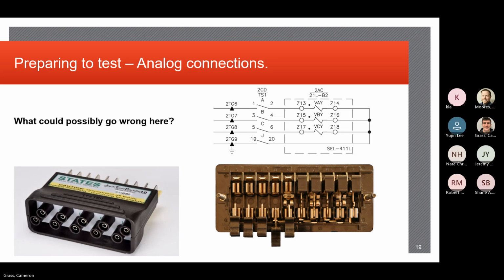Excellent. I guess one last point to that too, Brian, is a lot of the times, these relays could be bench tested, meaning that they do their relay testing without them actually being placed into the cabinet. So they're wiring all their voltages and currents directly to the back of the relay rather than plugging into these test switches that would be in the panel in this situation. So again, if that's the case, you've got to make sure you're doing your due diligence during your functional testing when you're actually wired in, everything's connected to the relay and whatnot, and verifying that your isolation parameters, in this case the knife switches, are in the correct polarity.